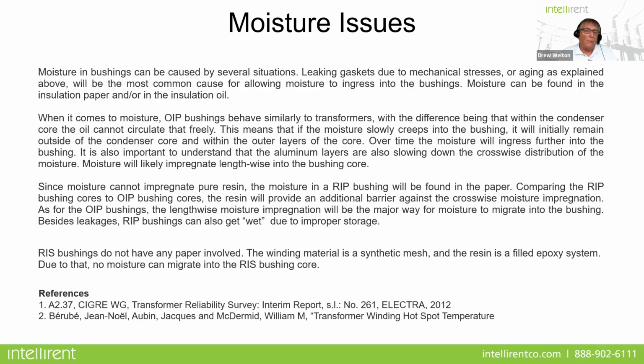Since moisture can't really impregnate pure resin, the moisture in an RIP bushing will be found strictly in the paper. So comparing RIP bushings to OIP bushing cores, the resin will provide an additional barrier against the crosswise moisture impregnation. As for the OIP bushings, the lengthwise moisture impregnation will be the major way for moisture to migrate into the bushing. So besides leakages, RIP bushings can also get wet due to improper storage.